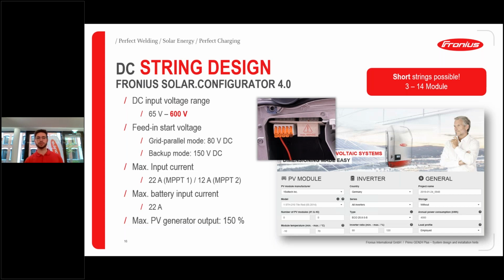However, we need to make sure, or we need to remember, that the feed-in start voltage on our products, the GEN24 products, in grid parallel mode is 80 volts. So we need at minimum 80 volts once, and then we can track down to 65 volts and up to 600 volts. So this is the start voltage.